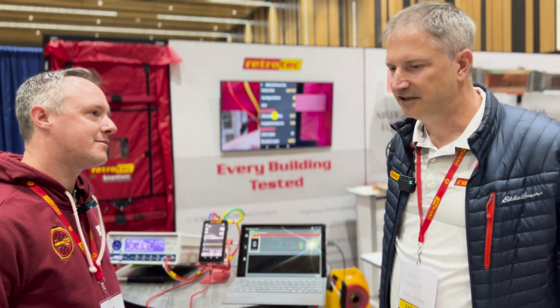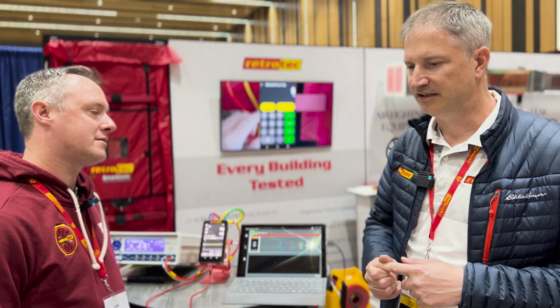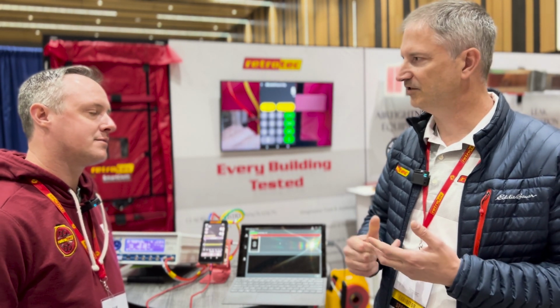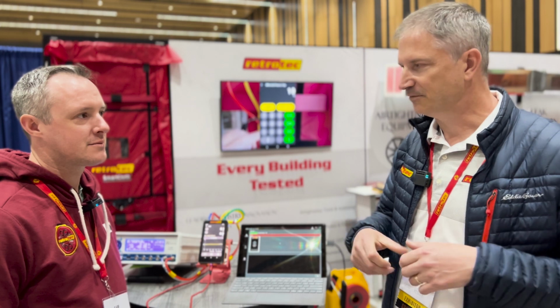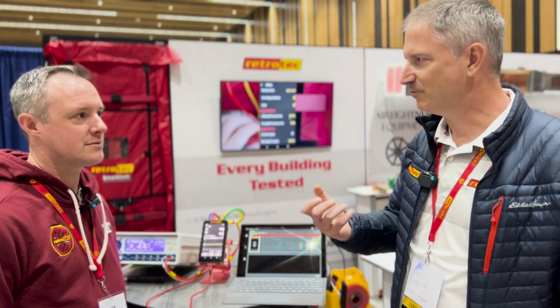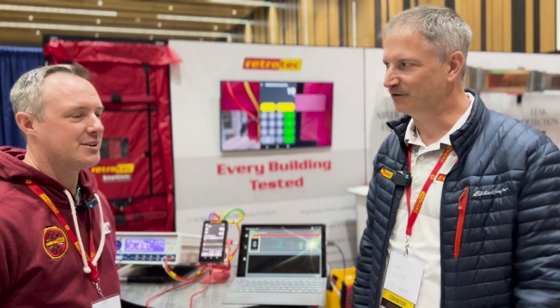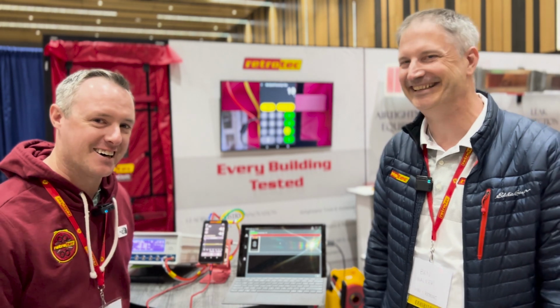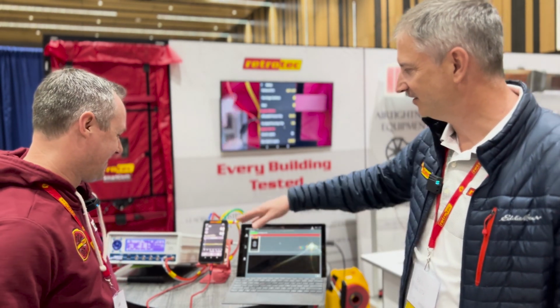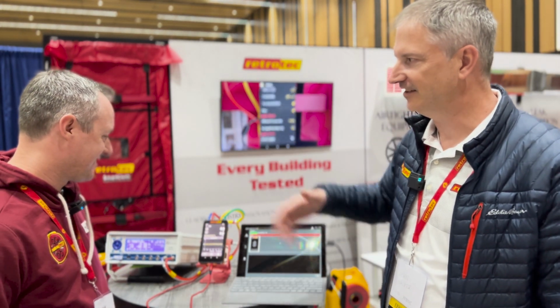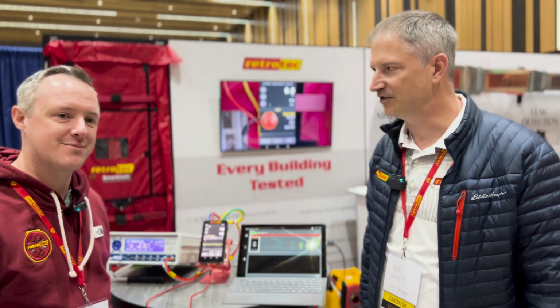And usually the sensors would have to see either electrical abuse, or sometimes people try to clean the tubes out with a high pressure PSI line or something like that, so that would burst the diaphragm. Don't do that. And you see that right away because the pressure readings on here will be vastly different than what you see on your reference device. So sure.